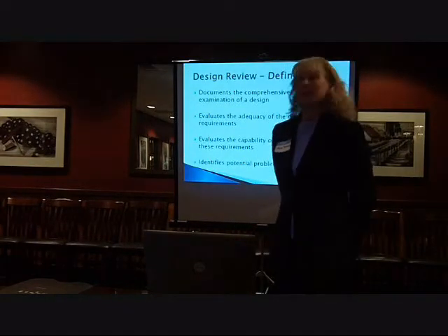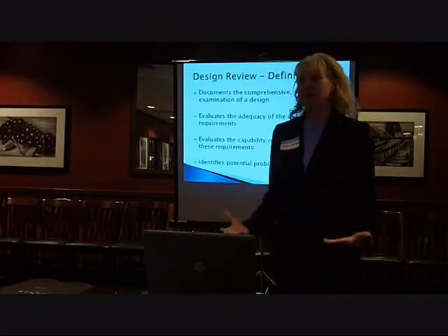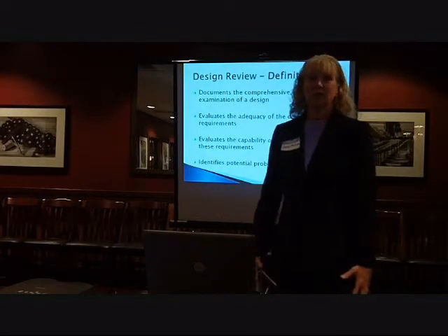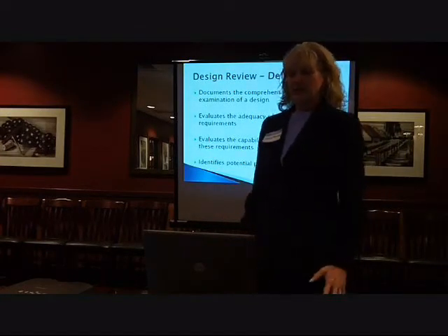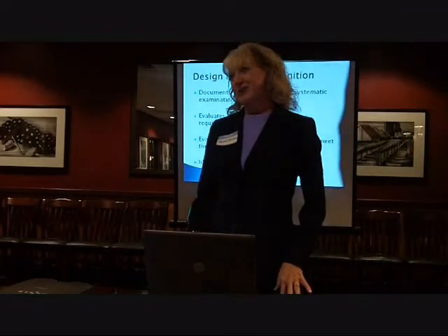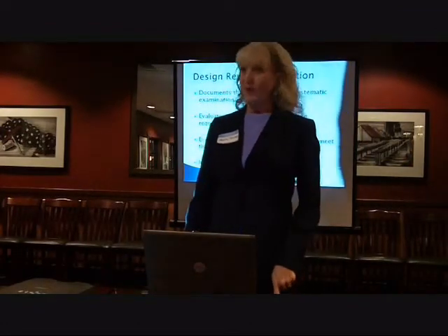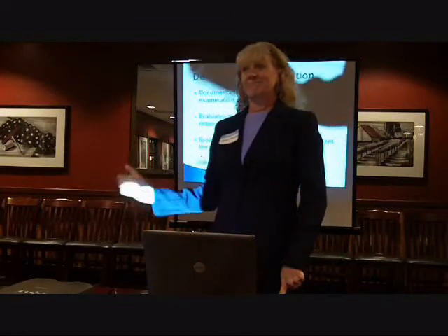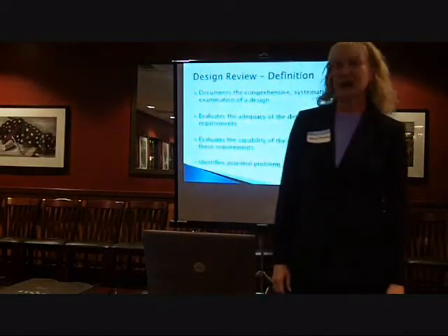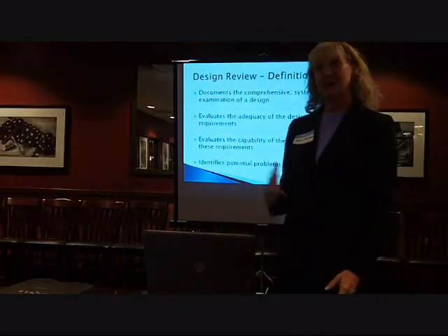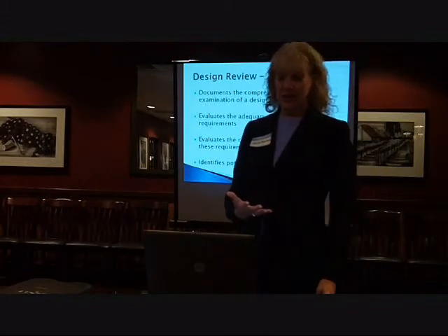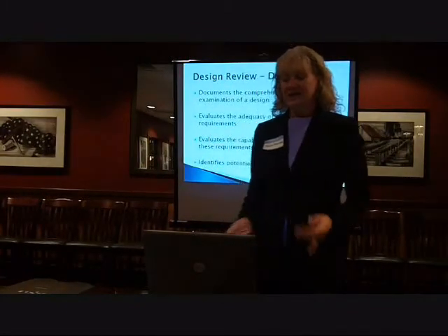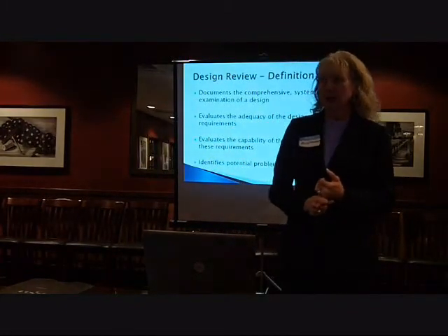Now that we have a design, the outputs, and all this documentation, we do a design review. Depending on how complicated your device is, you're going to do this once for sure, maybe 4, 5, 6 times, depending on how many times you go back and make changes to the design. So documentation is the biggest output here.